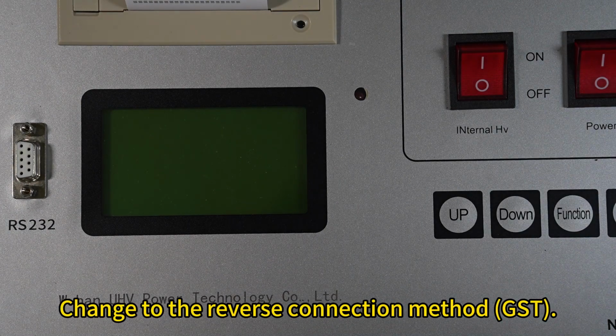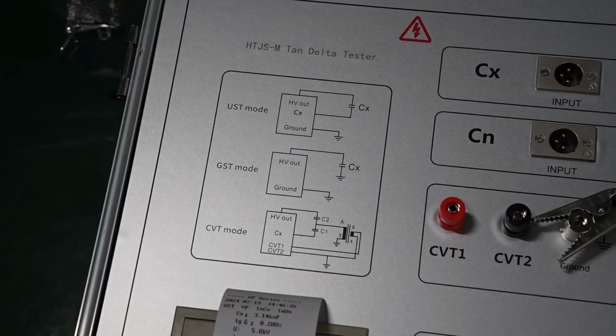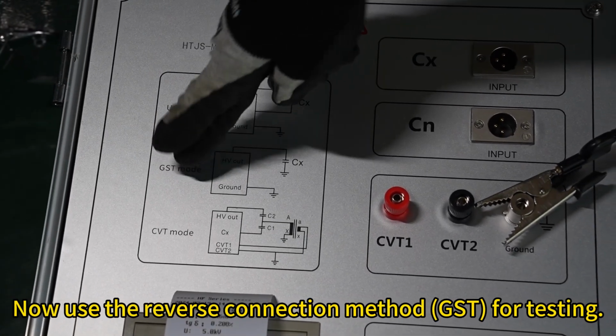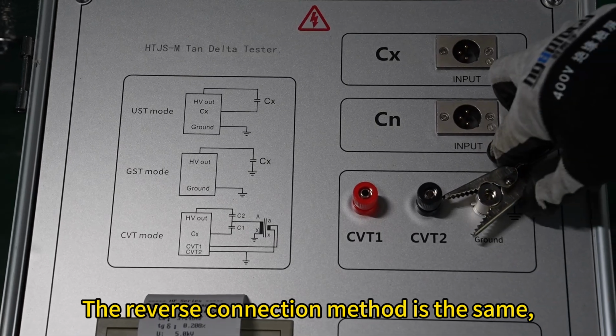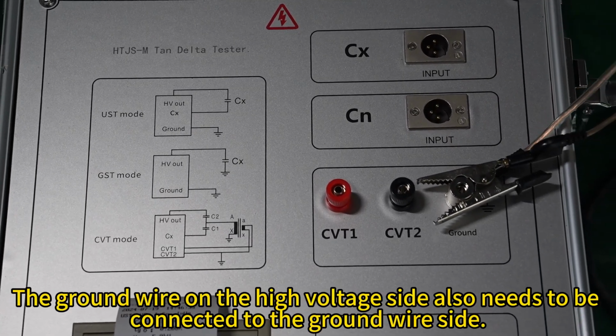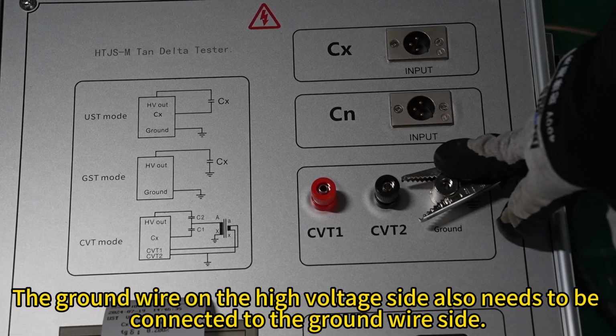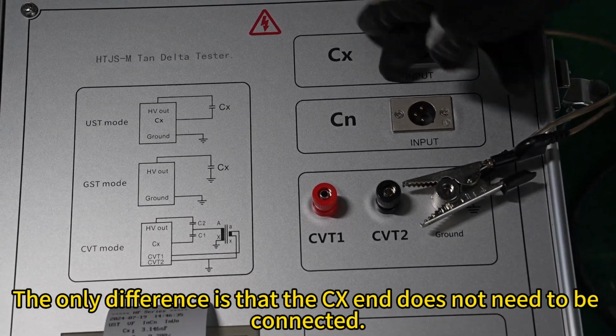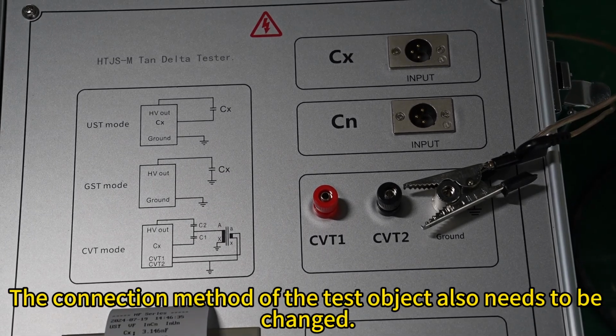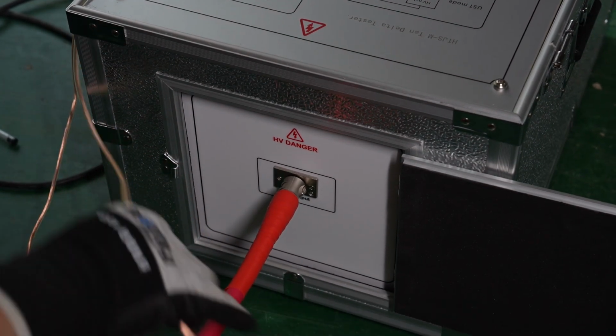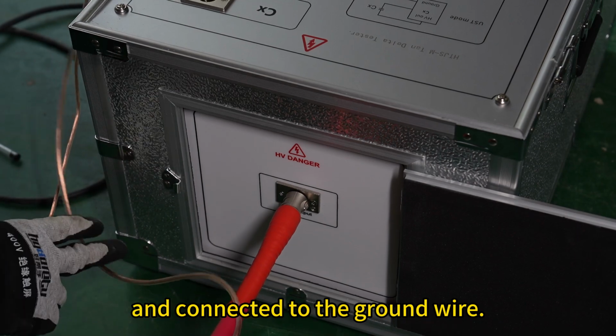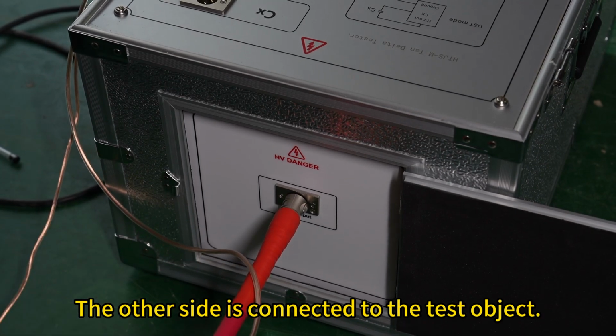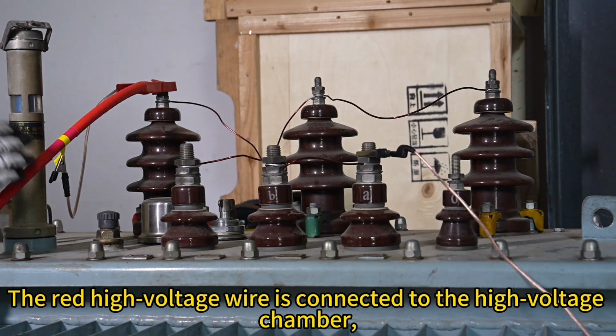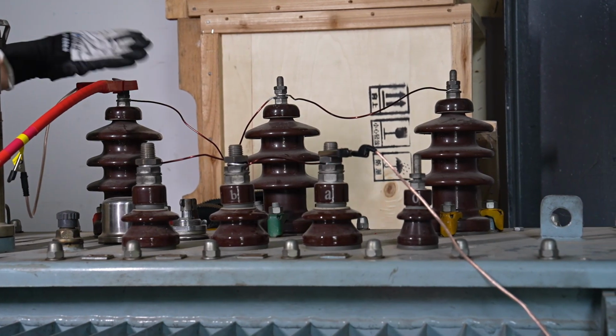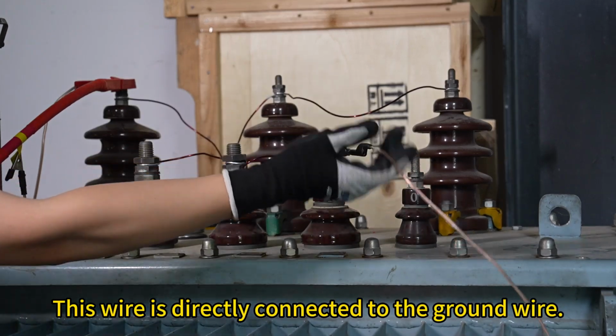Change to the reverse connection method, GST. Now use the reverse connection method, GST, for testing. The reverse connection method is the same, the instrument is grounded. The ground wire on the high voltage side also needs to be connected to the ground wire side. The only difference is that the CX end does not need to be connected. The connection method of the test object also needs to be changed. Connect the red high voltage wire here. A shielded wire is grounded here, and connected to the ground wire. The other side is connected to the test object. The red high voltage wire is connected to the high voltage chamber, and can be short-circuited. After short-circuiting, this wire is directly connected to the ground wire.